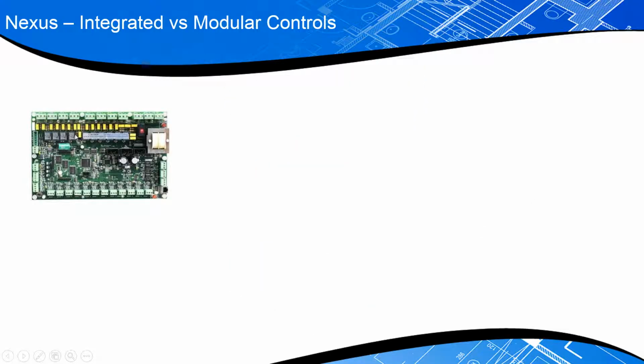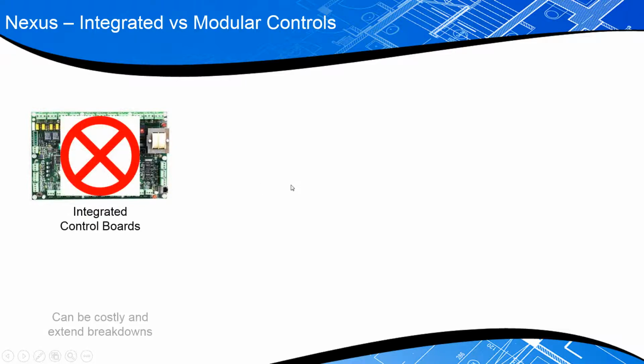The first thing I want to point out is the differences in architecture versus what's out there on the market. This is one of our major competitors' printed circuit board. The transformer, the power supply, and all these yellow squares are individual relays that turn on compressors, pumps, fan motors, and things like that. All of these components, the inputs and outputs, are hard soldered onto this printed board. The downside is that if you have a failure of any one of these components, your only option is to replace the entire board. This particular board probably runs about $1,200.